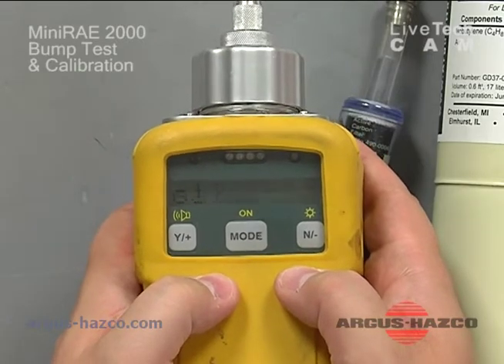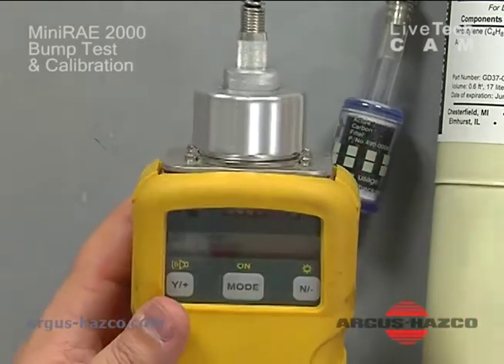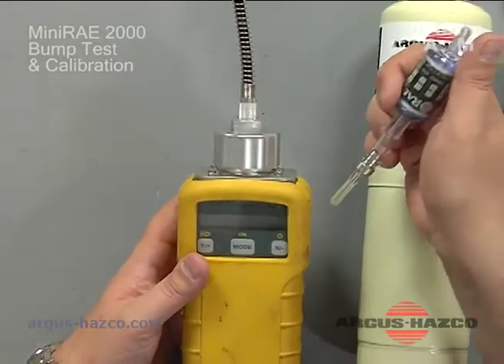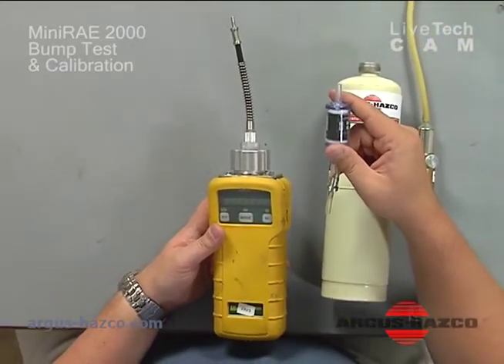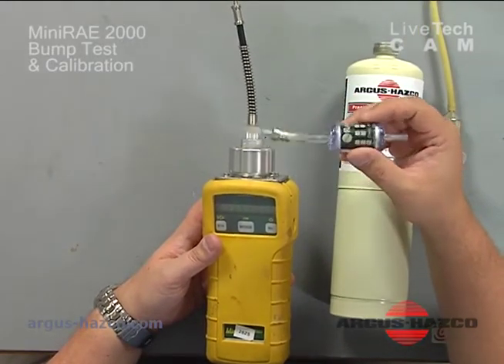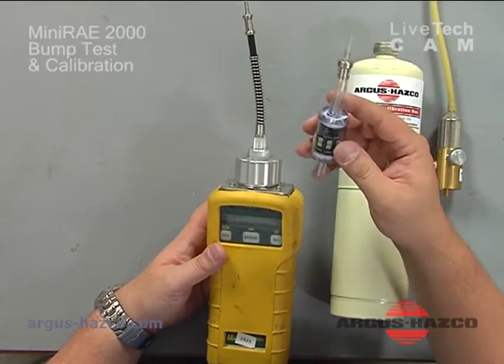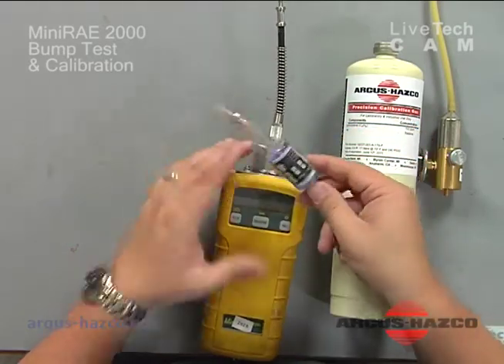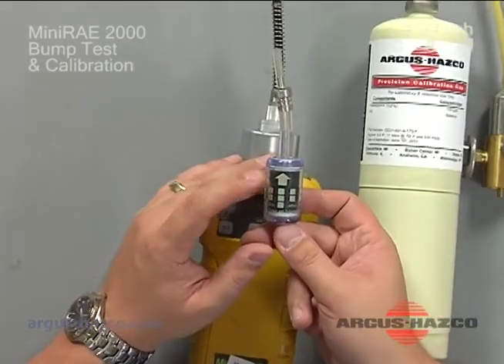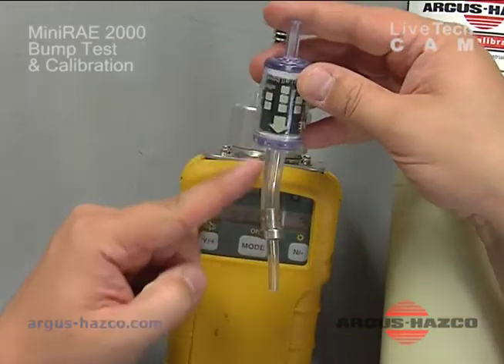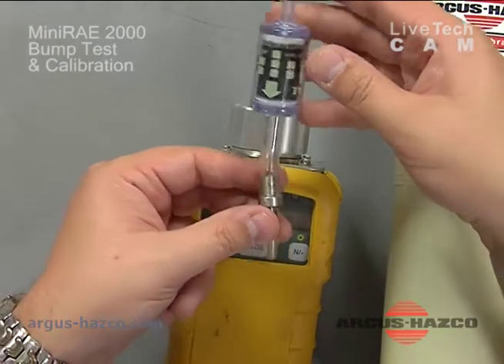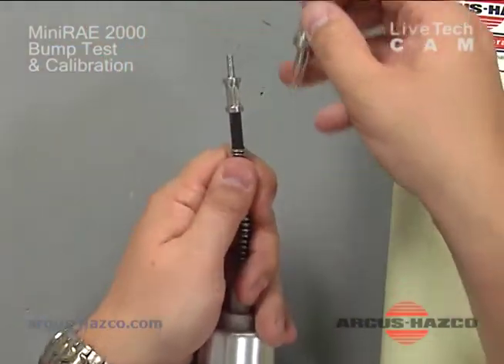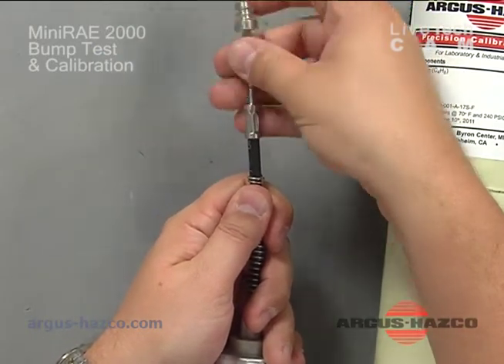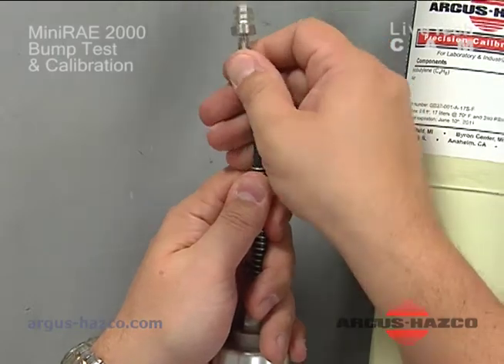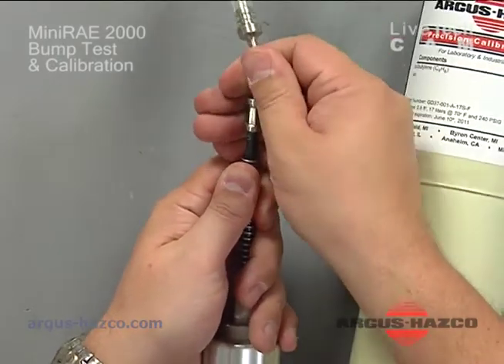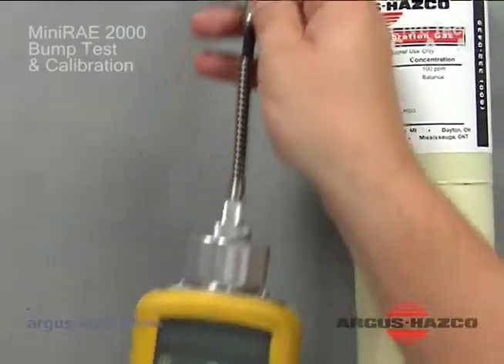It's asking, do you want a fresh air cal? Before you do this, if you know you're not in a fresh air environment, contaminant-free air, they have a charcoal scrubber filter that you can hook up to the inlet to ensure that you're getting a 0 reading. And again, on this filter you have an arrow that's indicating the sample flow. So you want the sample flow to be coming into your MiniRAE 2000. So we have the tubing set on this side, and we're going to take that filter and put it on the end, like so.